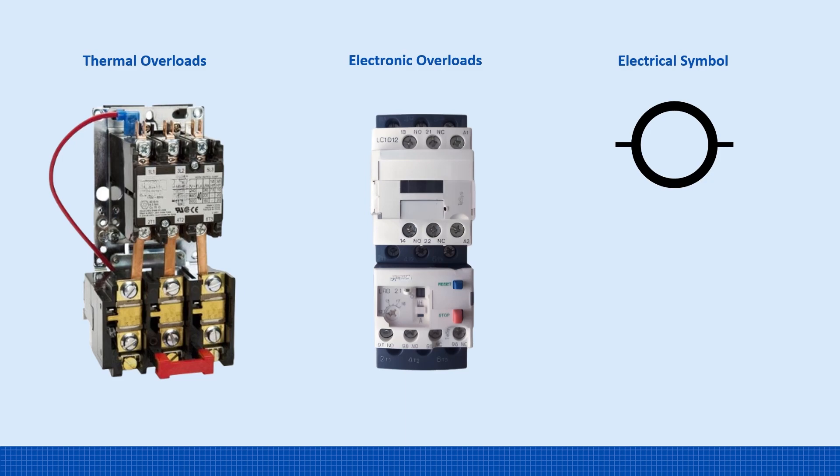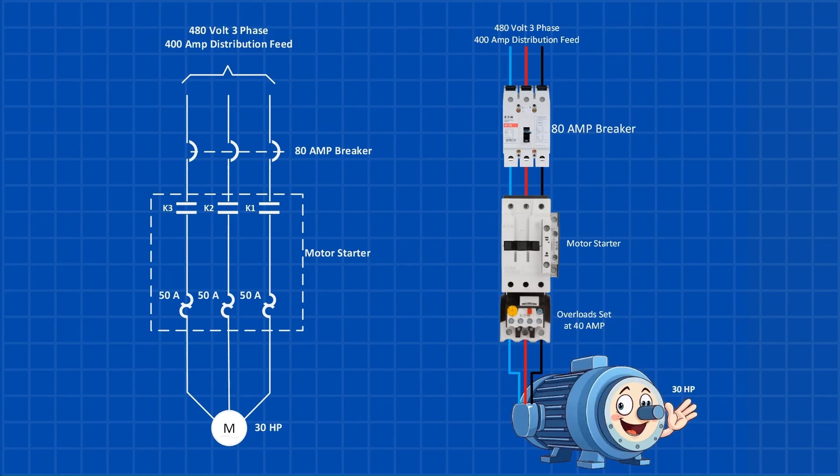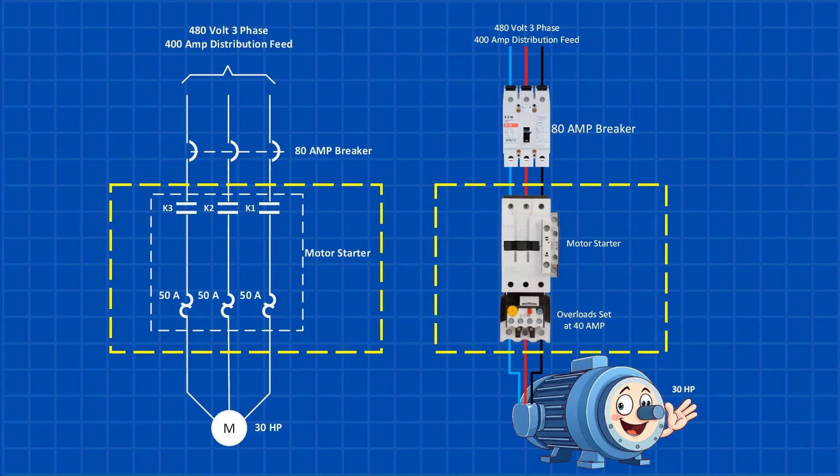So what exactly is a motor starter? A motor starter is simply a contactor with an overload protection device attached to it. There are two main types of starters: those with thermal overloads and those with electronic overloads. To start a three-phase motor, all three phases need to be powered simultaneously, and that's where a motor starter comes into play. It has three contacts that close at the same time to send power to the motor. The motor starter also includes overload protection. If the motor draws too much current beyond the set limit, the overload protection trips, cutting off power to prevent motor damage.